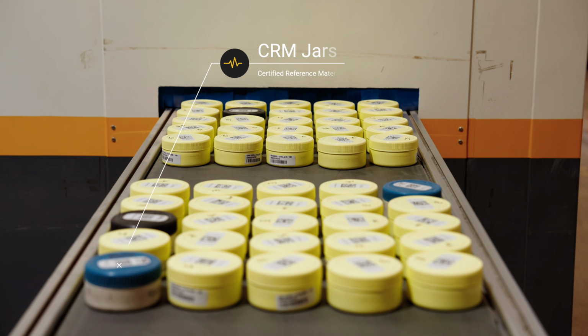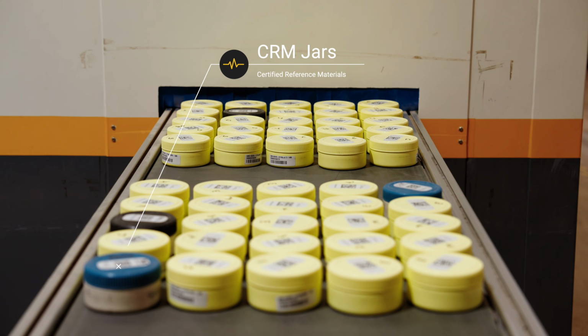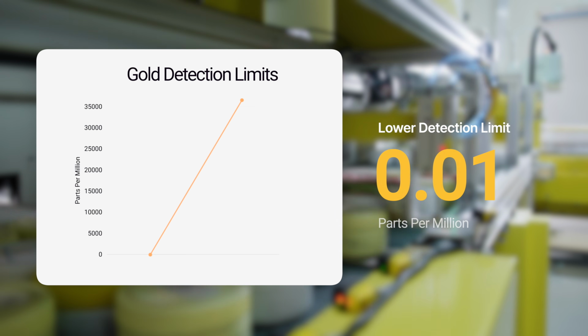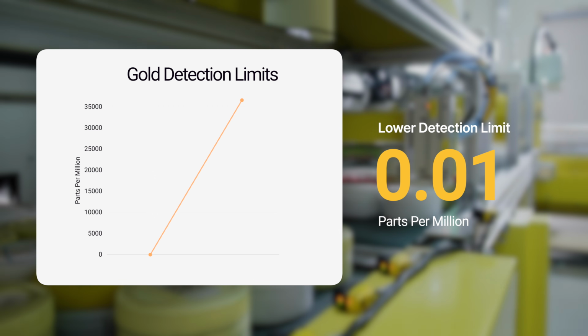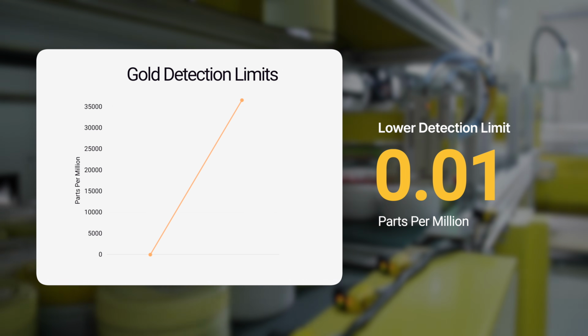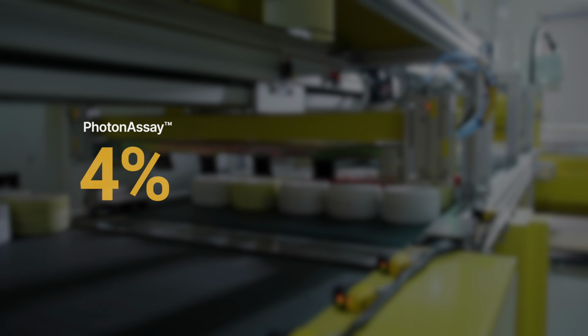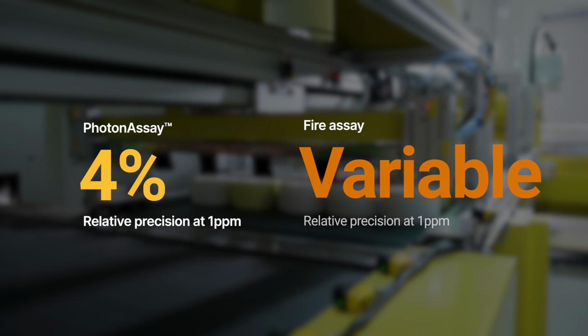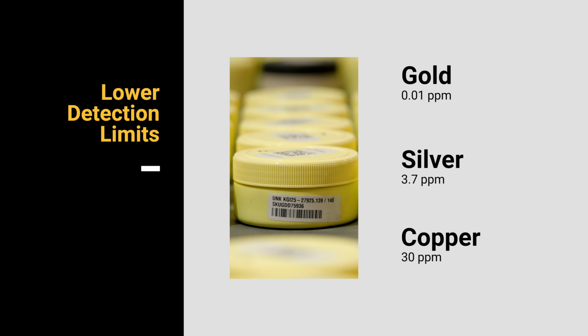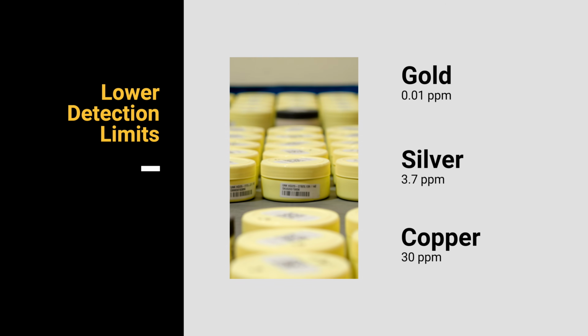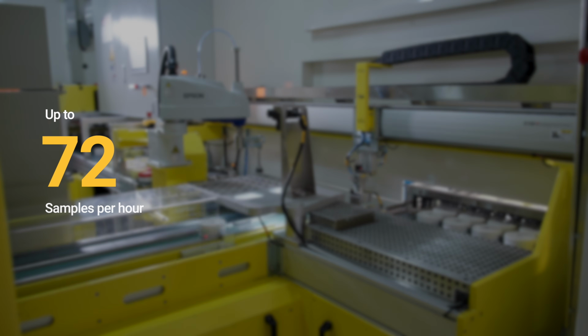Extensive comparisons across a range of certified reference materials show excellent agreement with PhotonAssay for all ore types and grades, with a correlation greater than 0.99. For gold, the lower limit of detection reaches 0.01 parts per million, or ppm, and samples up to 35,000 ppm can be measured. The relative precision is around 4% at 1 ppm, comparable to PhotonAssay at the same grade. For silver, the detection limit is around 3.7 ppm, and for copper, about 30 ppm, with excellent linearity across the analysis range. Each unit can process up to 72 samples per hour.